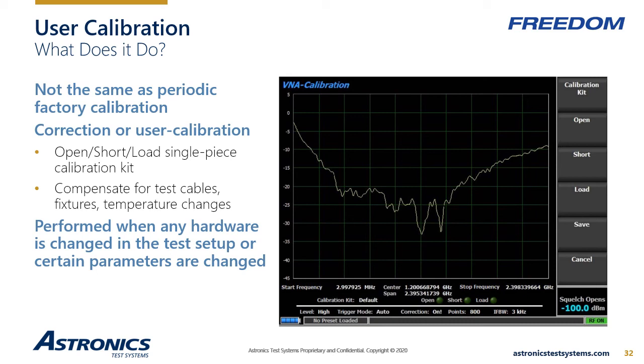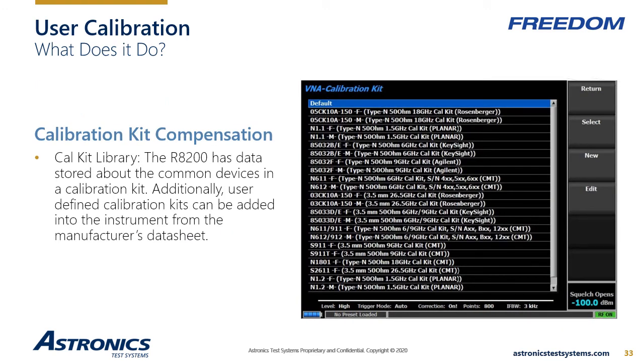When a system parameter is changed in the plots or distance default, that potentially invalidates the calibration, and so the instrument displays a calibration status warning to remind the user to recalibrate the VNA. For the ultimate accuracy, a user can provide information about the calibration kit to compensate for its slight impedance mismatches. There's no such thing as a perfect open or short or load. The calibration kit's manufacturer provides a datasheet with all the relevant parameters. The FREEDOM R8200 provides a library for the most commonly used calibration kits, including the one that is included with the instrument. However, the user can add a custom cal kit to the library for later reference.